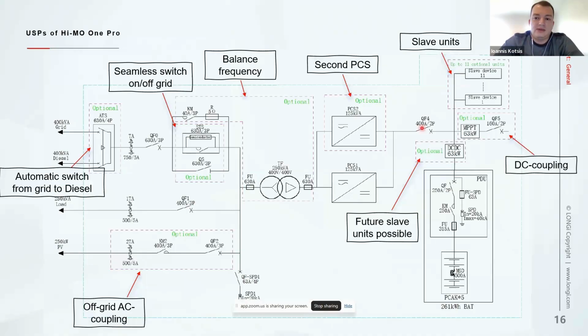So after this, we go to the PCS. Here you can see, after the battery, we have the 125 kilowatt PCS. The second PCS also is optional. I should add that we can have up to 11 slave units. This is the maximum. So yeah, the maximum is 1 master and 11 slave units. So all adds up to 3 megawatt hours of capacity. So we have the PCS, and then we come to the transformer. That is optional if we want the STS function. So less than 20 milliseconds to backup. Here you see the seamless. And here we have the grid and the loads.